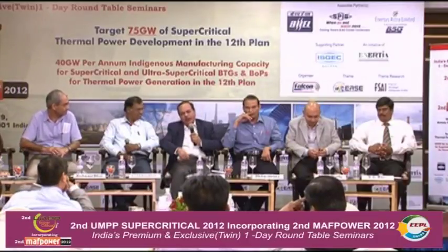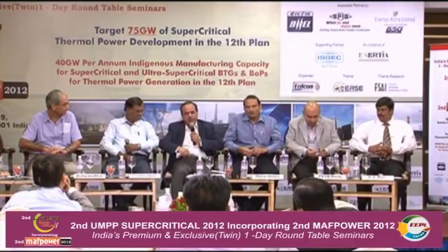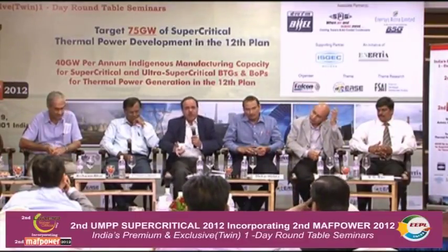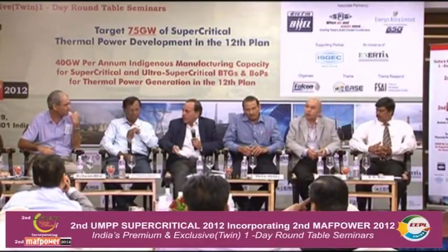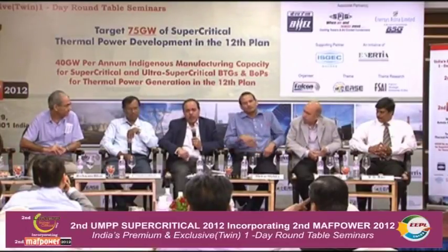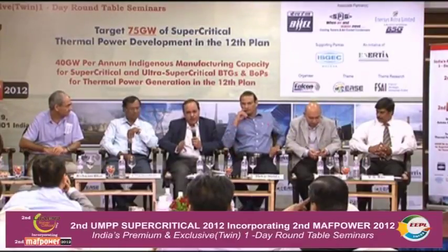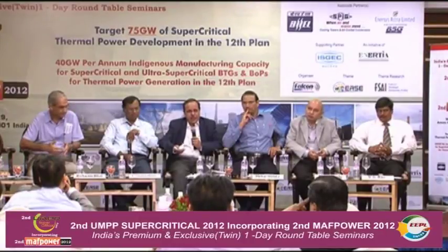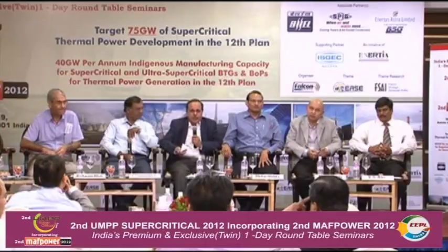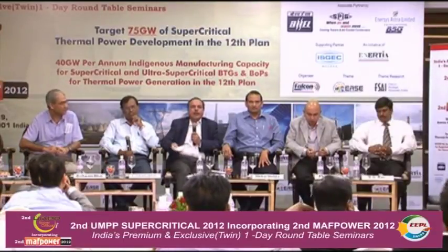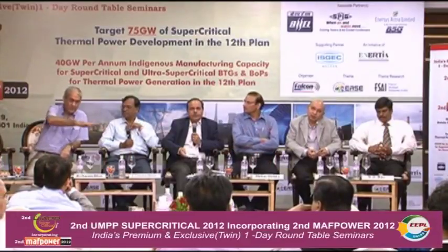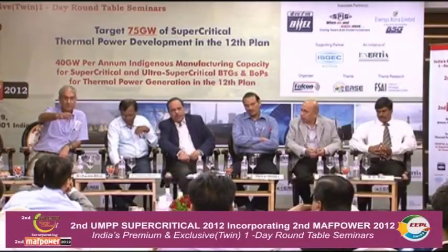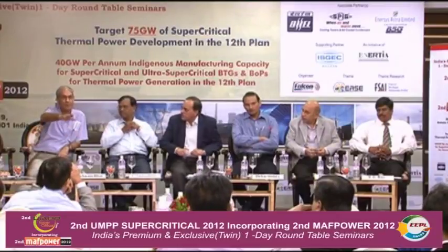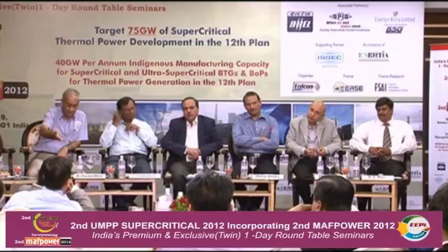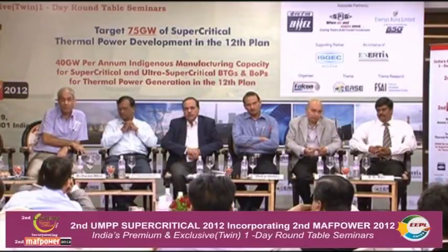Let me tell you about the old plants. Take the Russian plants, which are maximum in number since BHEL did the most of them, so 210 megawatt or 110 megawatt plants are mostly Russian. Now look at the heat rates, turbine heat rate, and boiler efficiency of those plants. Even if you upgrade by 10% with similar heat rates, it's still not viable, certainly not possible. So it's better to replace and shut that down, because if you look at the overall economic factors, the final cost will be much higher than the R&M issue. With carbon credits you get a new, much better, very low heat rate, and also save a lot on coal.